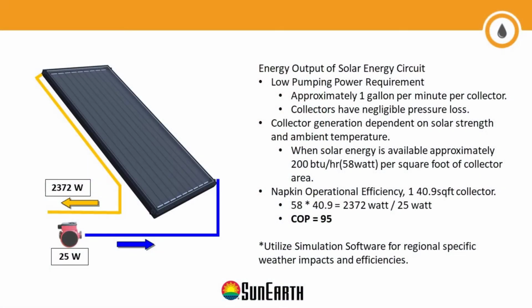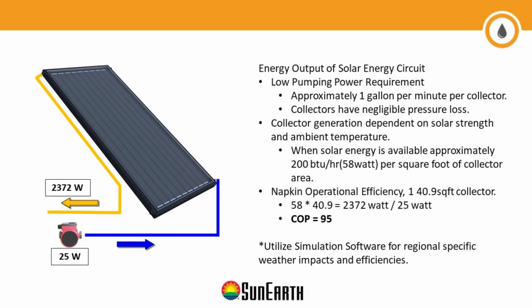So on top of the per square foot, solar to solar, right? We want to talk a little bit about some of the advantages of why solar thermal would be advantageous as an energy source for hydronic applications. So they require very low pumping power, generally around 1 gallon per minute as a flow rate per collector. The generation of the collector really depends on the ambient temperature and how much sun is out, different things like that. It's variable, but if you're just trying to estimate pretty quickly, we're going to look at about 200 BTUs per hour per square foot, right? The solar energy is around 318 BTUs per hour per square foot in full sun.